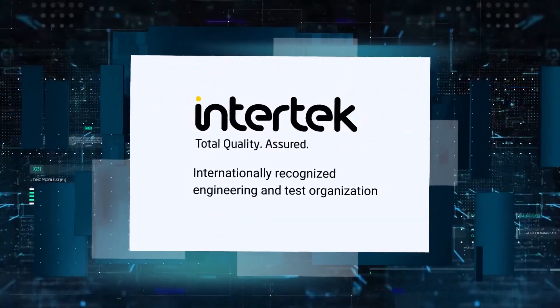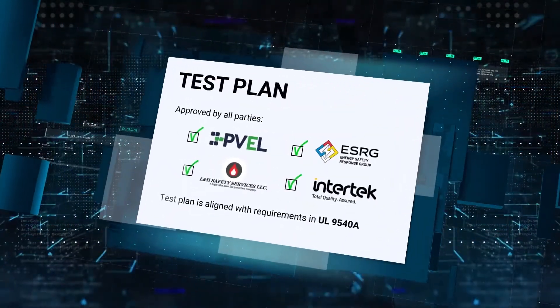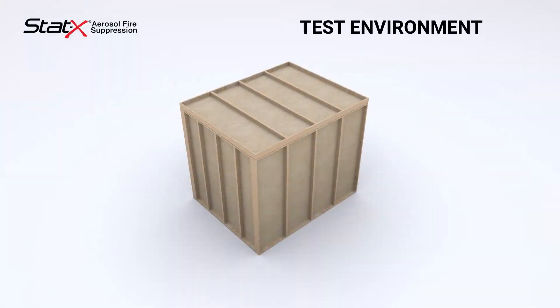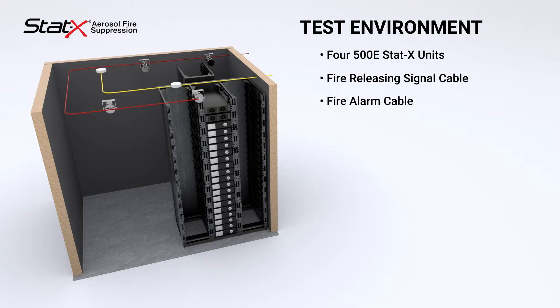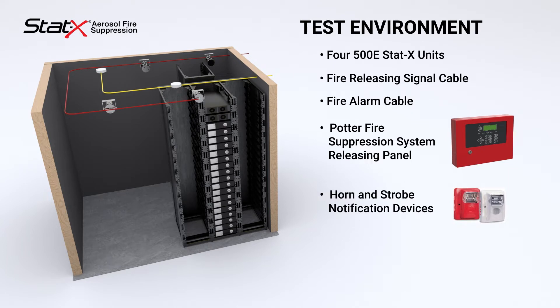Intertek, an internationally recognized engineering and test organization. The test plan was approved by all parties and is aligned with requirements in UL 9540A. The test environment consisted of a 2.3 meters wide by 2.5 meters long enclosure with four 500E Stat-X units, fire releasing signal cable, fire alarm cable, a Potter fire suppression system releasing panel, horn and strobe notification devices, two photoelectric first and second smoke detectors providing cross-zone detection, and a manual release pull station.